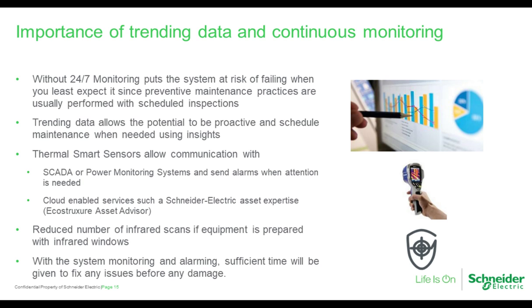And then there are cloud-enabled services, such as from Schneider, that can look at all of these different devices and give expert opinion on what's going on with the system. Again, like I indicated before, just because the temperature is rising doesn't mean there's something wrong with the system. There could be a rise in the load also. And we need to compare the rise in the load and the rise in the temperature to see if it's an issue with a connection or if it's just a normal operational issue.